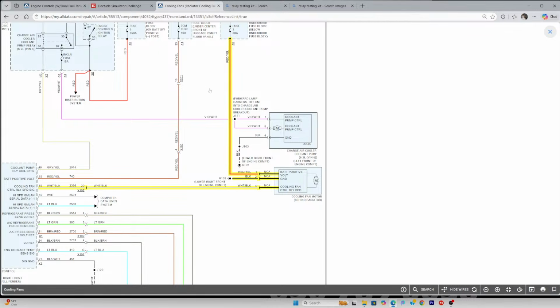So if your voltage is good and your ground is good, disconnect it. If you disconnect it and you get an open circuit code here, if your code changes to signal control high voltage or open circuit, if it changes, most likely you're dealing with a defective cooling fan motor.